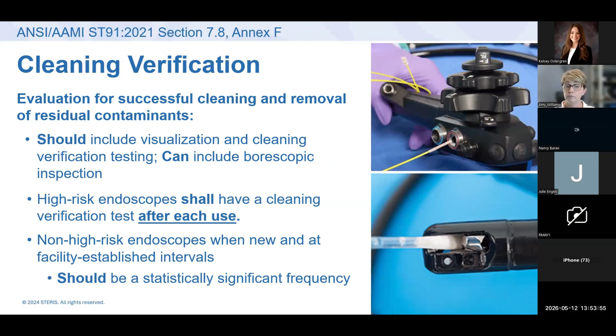Repeated cleaning failures, cleaning verification failures indicate the scope is probably damaged. So if you're failing your ATP or your protein test, if that device is failing, it's probably broken. So pull it out of service. That should be in your policy as well.